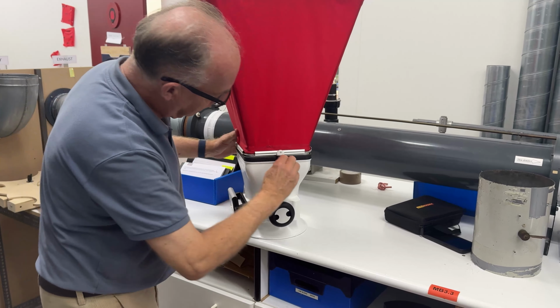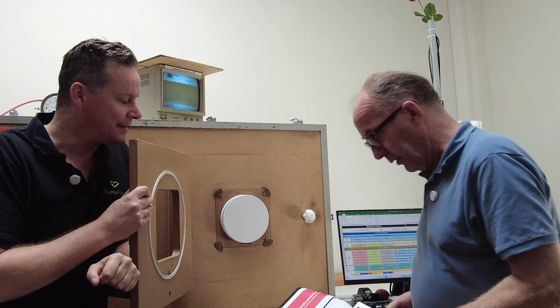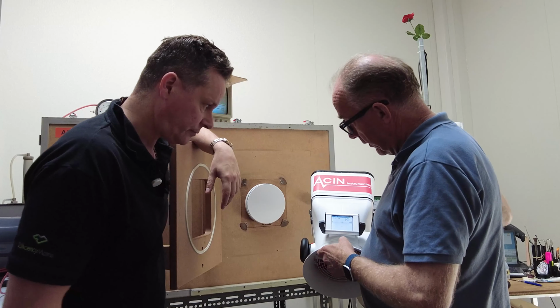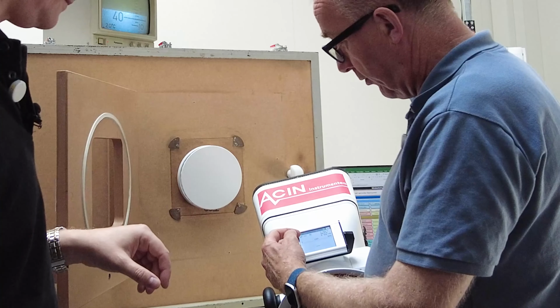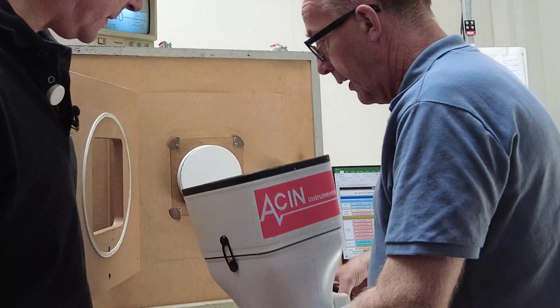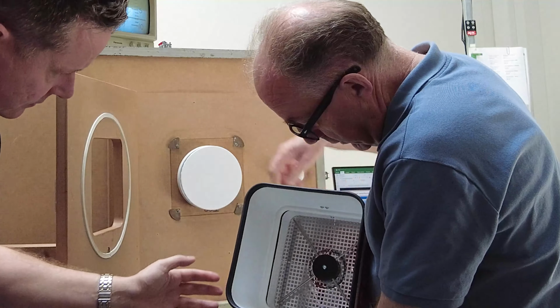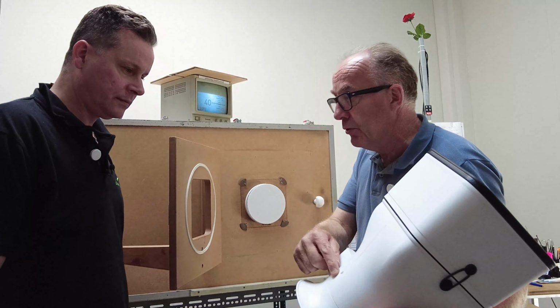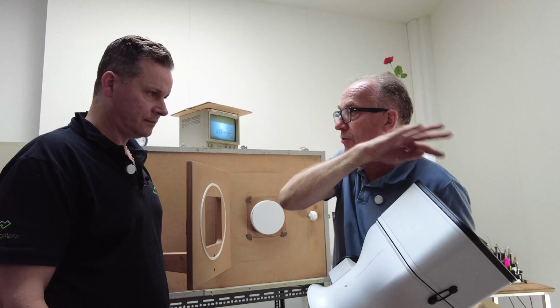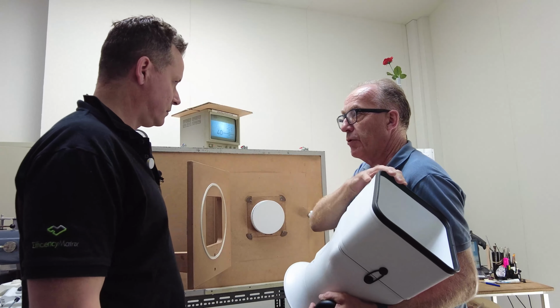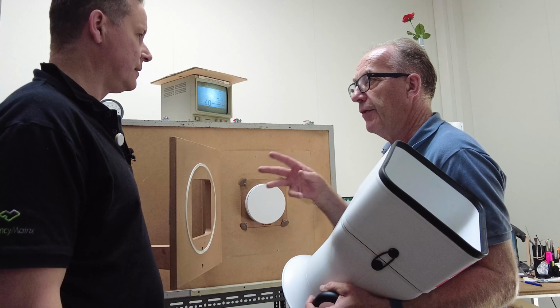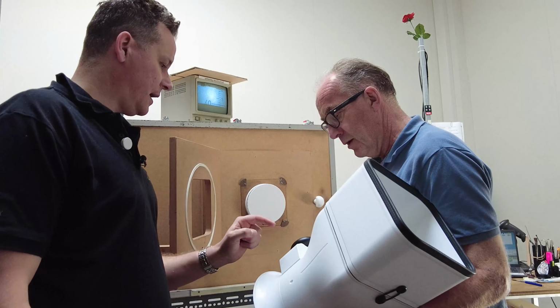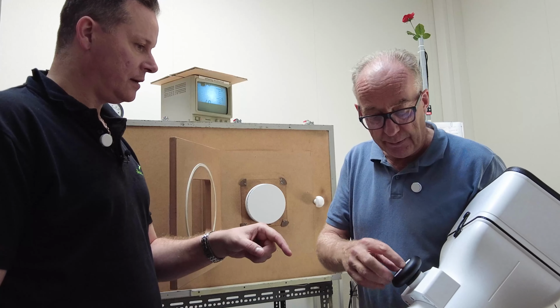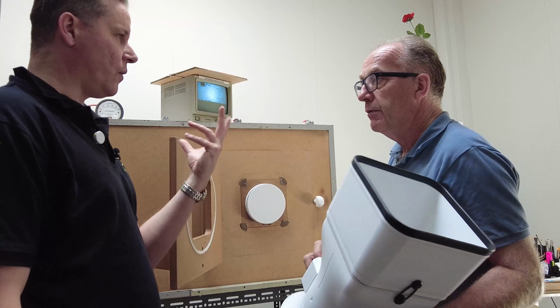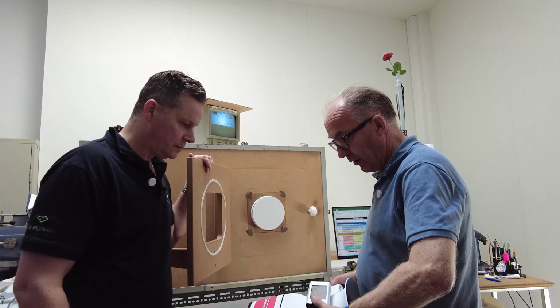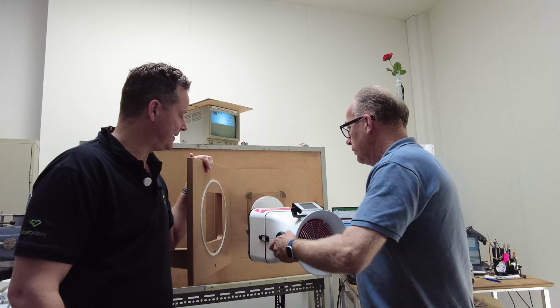With your beautiful Flowfinder. Let's first start with the Flowfinder. Here you have a screen. I don't know how well you can read it, but the most important thing here is the differential pressure. The differential pressure is measured in the hood with these pitot tubes against this hole in the back. So differential pressure outside, inside. Supply flow, you will get a positive pressure in the hood. Exhaust flow, you will get a negative pressure in the hood. And this is the battery. The fan inside it can operate either way, negative or positive pressure. The sign of the pressure will give you the direction of the flow.